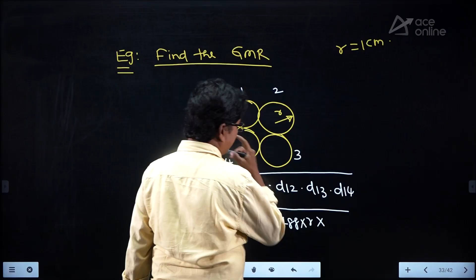So GMR means first one, second one, third one and fourth one. D11, D12, D13, D14. So how many distances? 1, 2, 3, 4. 4 distances, fourth root you have to take. So it will be fourth root of D11, it is 0.7788 into R. R is 1, into distance from 1 to 2, 2R. Distance from 1 to 3, 2 root 2R. Distance from 1 to 4, 2R. They are the radius, right? So it will be fourth root of 0.7788 into 1 into 2 into 2 root 2 into 2. It will be 1.723 centimeters. Like that you can calculate, right?